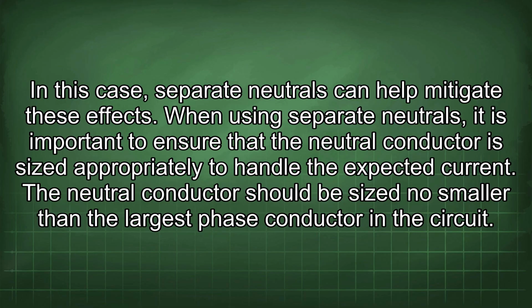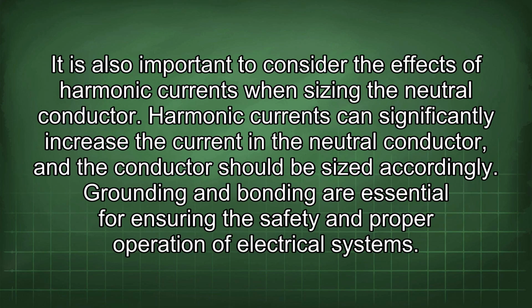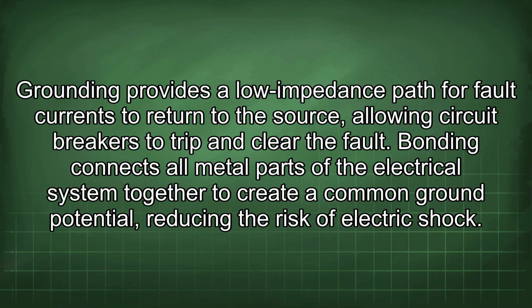When using separate neutrals, it is important to ensure that the neutral conductor is sized appropriately to handle the expected current. The neutral conductor should be sized no smaller than the largest phase conductor in the circuit. It is also important to consider the effects of harmonic currents when sizing the neutral conductor. Harmonic currents can significantly increase the current in the neutral conductor, and the conductor should be sized accordingly. Grounding and bonding are essential for ensuring the safety and proper operation of electrical systems. Grounding provides a low impedance path for fault currents to return to the source, allowing circuit breakers to trip and clear the fault. Bonding connects all metal parts of the electrical system together to create a common ground potential, reducing the risk of electric shock.